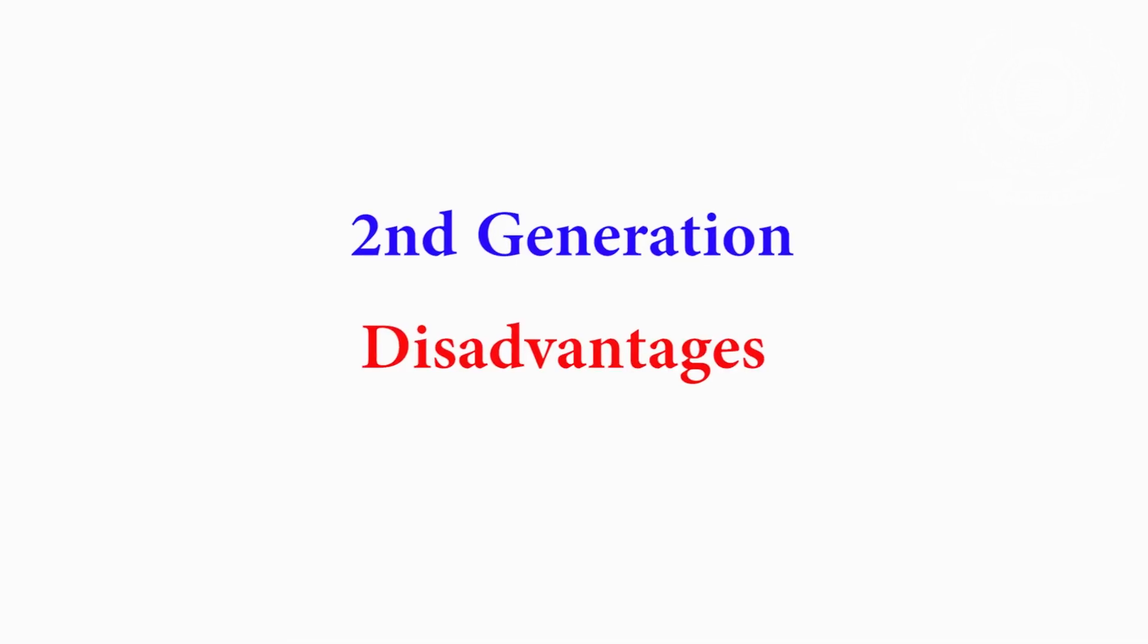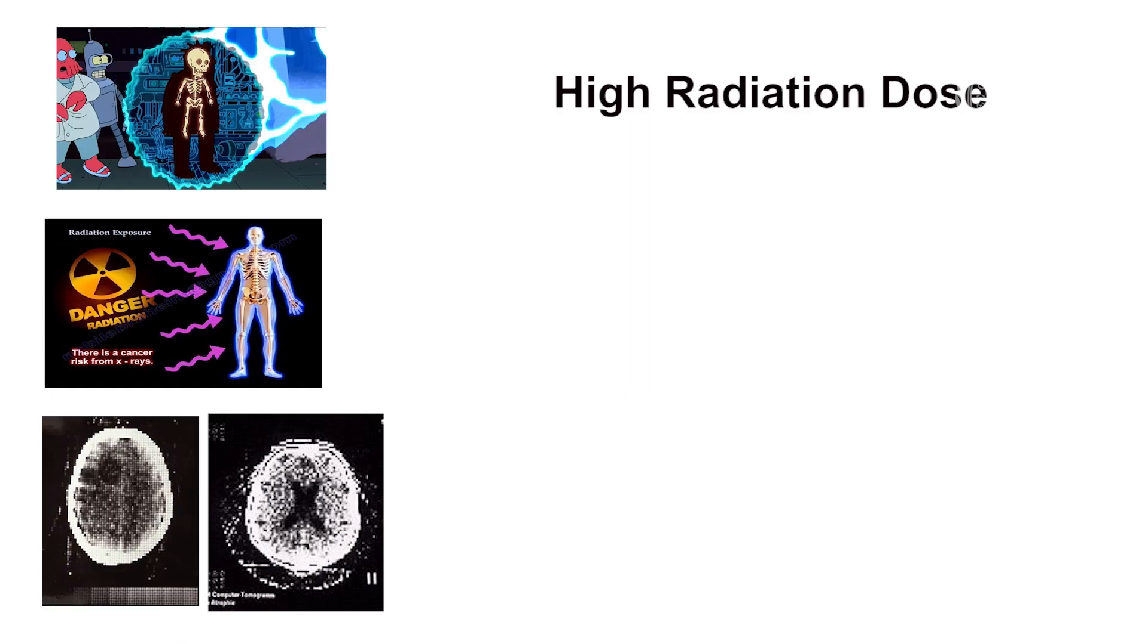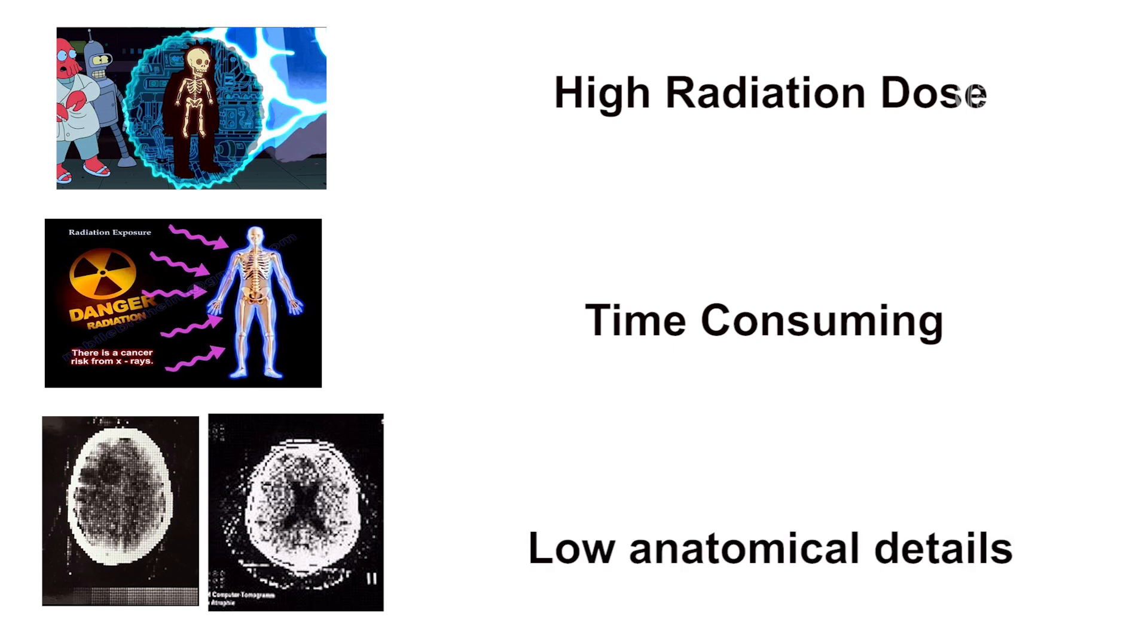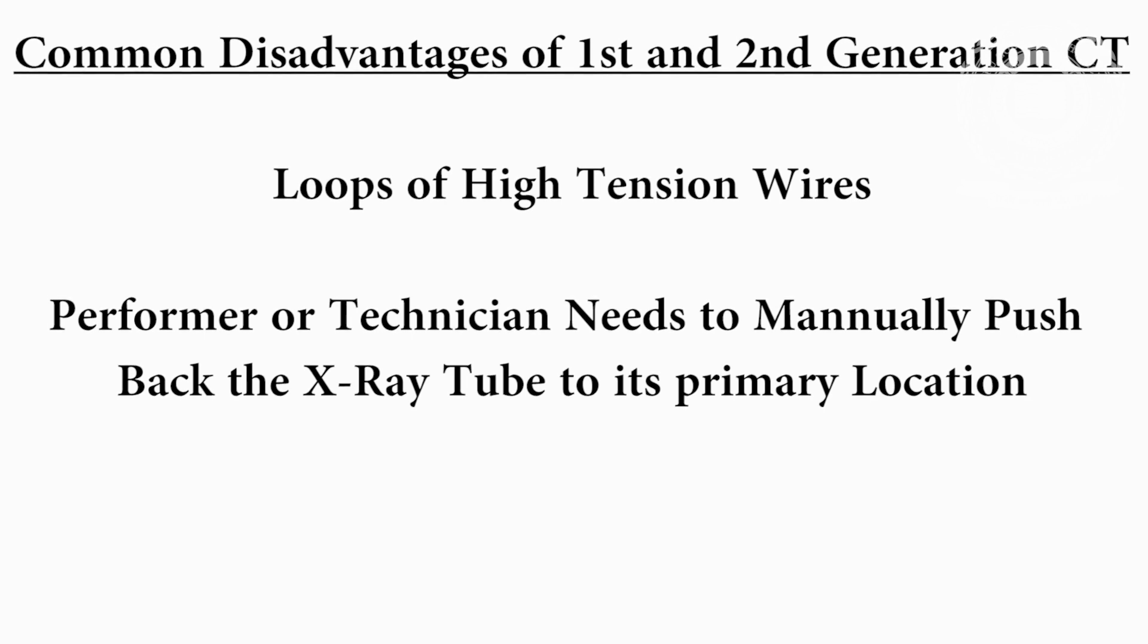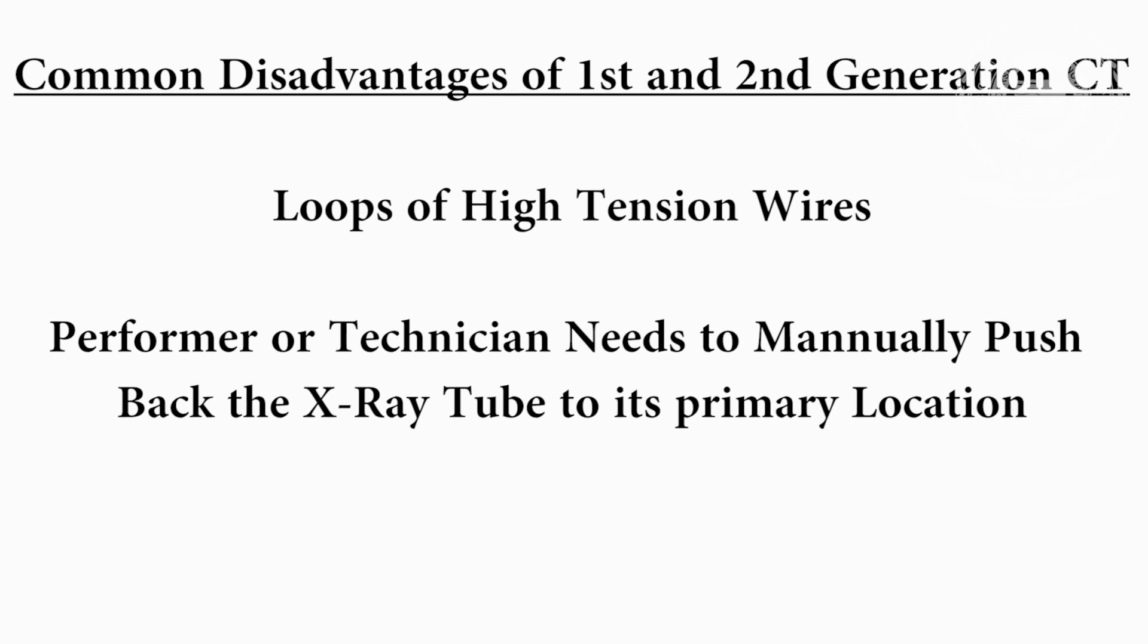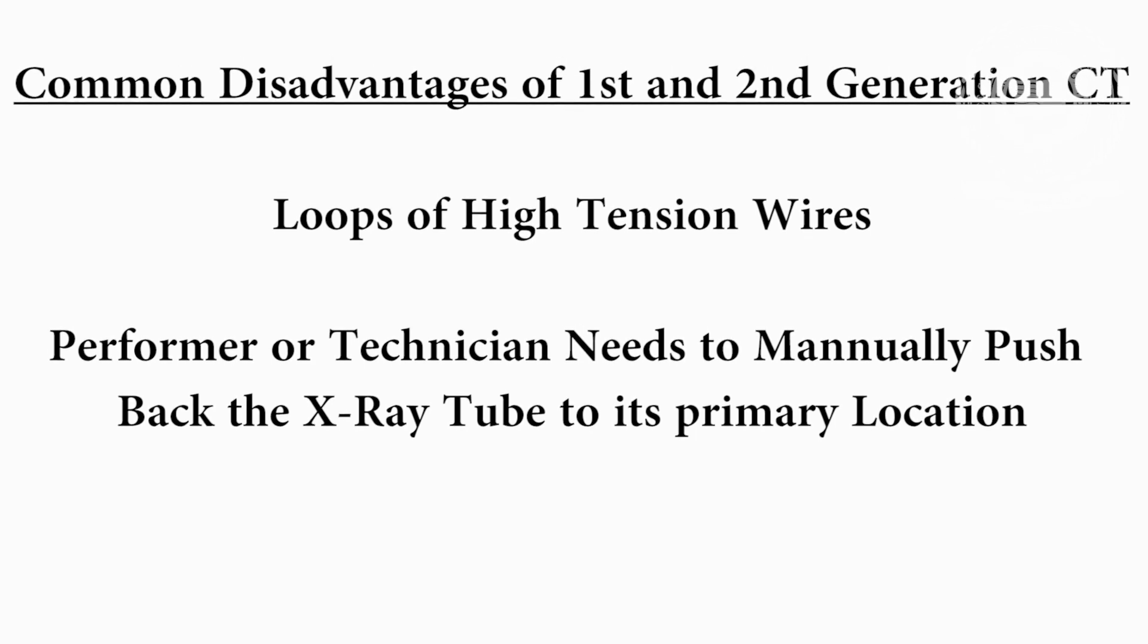But the other disadvantages of first generation were not rectified like high radiation dose, long scan time, poor image reconstruction technique, and still low anatomical details. One more thing, there is one common disadvantage in both generations and that was loop of high tension wires due to lack of 360 degree rotation of X-ray tube in the gantry.